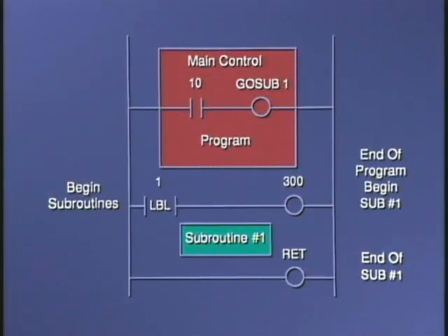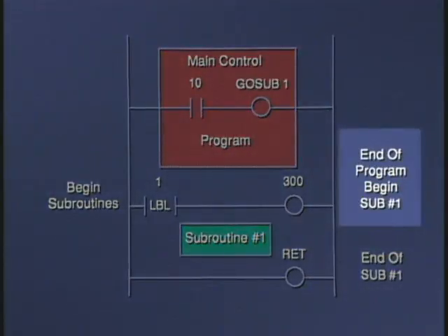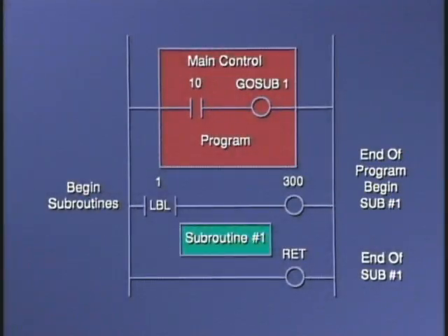This instruction is very useful whenever a routine in the program may be recalled by several sections of the main control program for operations such as mathematical computations, or if the routine may be called on a timely basis for specific functions, such as an interpolation of the nonlinear analog input. Subroutines, because of their use, are generally located at the end of the control program in order to keep better organization of the control software.